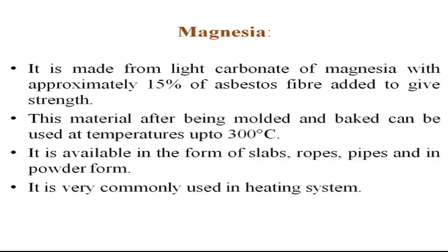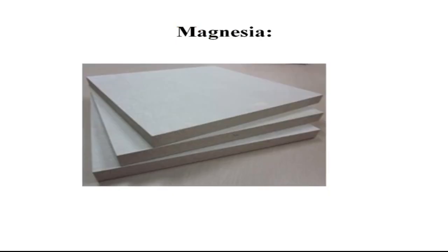Magnesia is made from light carbonate of magnesia with approximately 15% asbestos fibers added to give strength, since magnesia itself is a powder with no structural strength. After being molded and baked, it can be used at temperatures up to 300°C as it has nothing that burns at that temperature. It is available in the form of slabs, ropes, pipes, and powder form, and is very commonly used in heating systems.